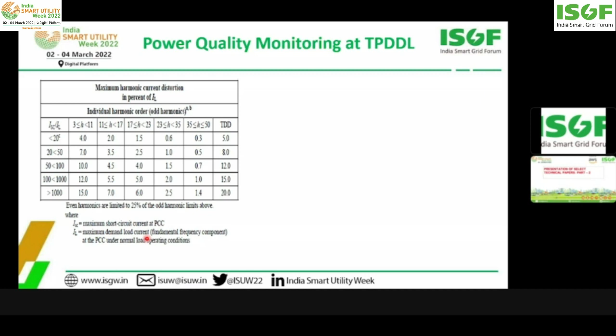Calculate it depending upon by calculating this ratio ISC by IL ratio, where ISC is the maximum short circuit current at the PCC point, and IL is the maximum demand load current, which is calculated by taking average of preceding 12 months maximum current, which we can get from the electricity bill of the consumer. And to carry out this study, we used portable power quality meter, PQ Box 150. And to analyze the recorded data, we used WinPQ mobile software pertaining to this analyzer.